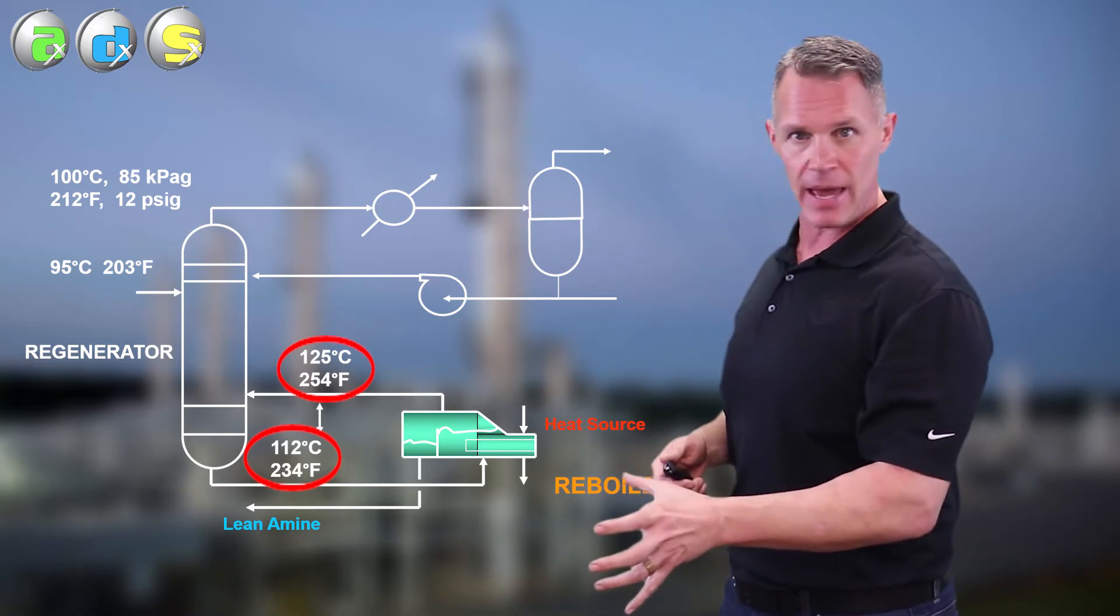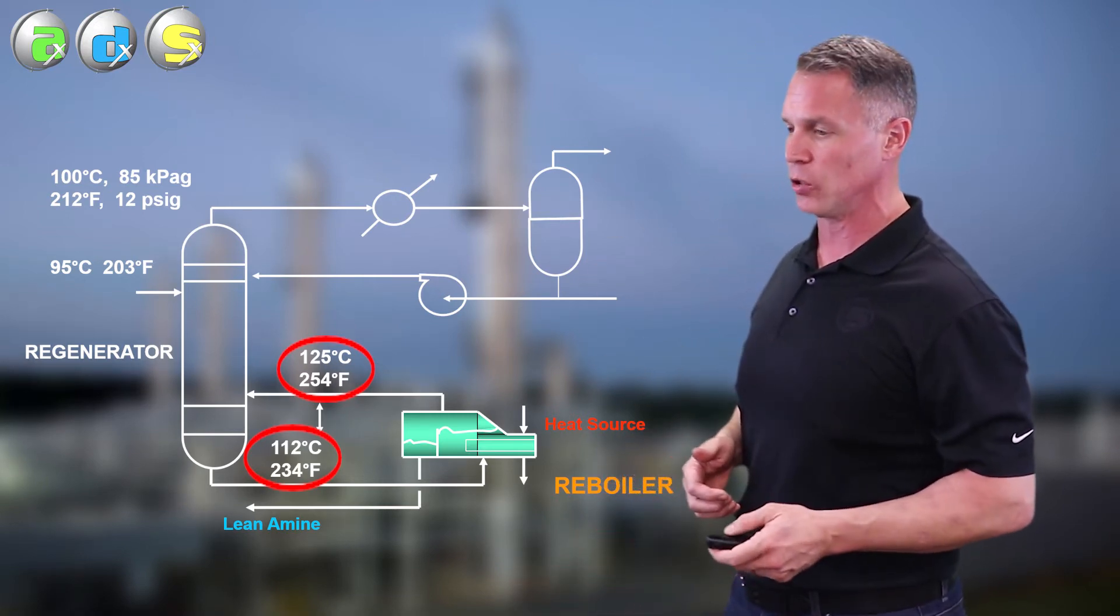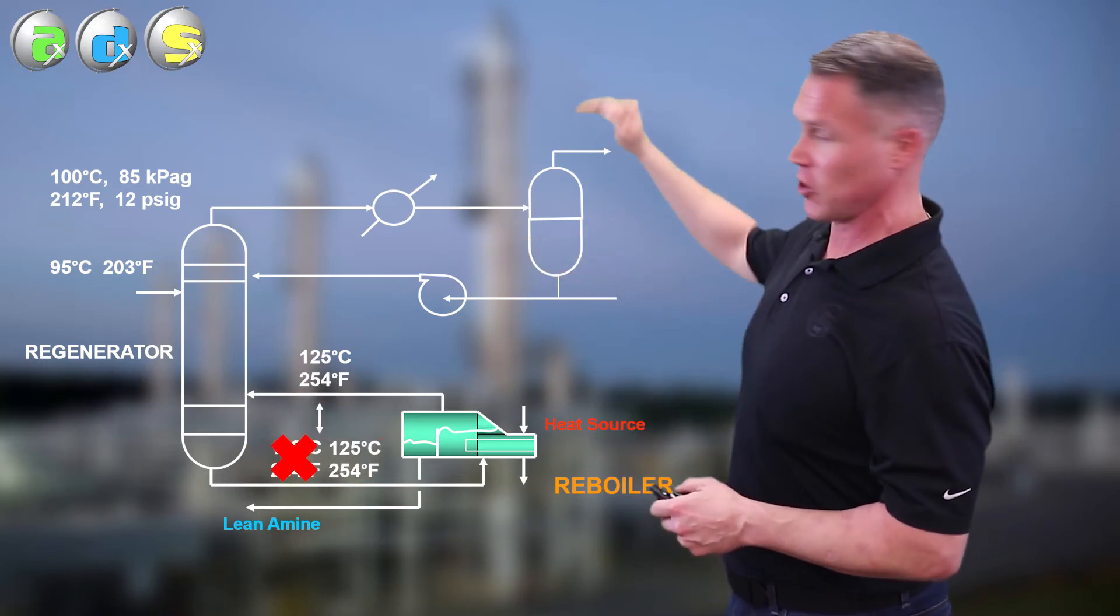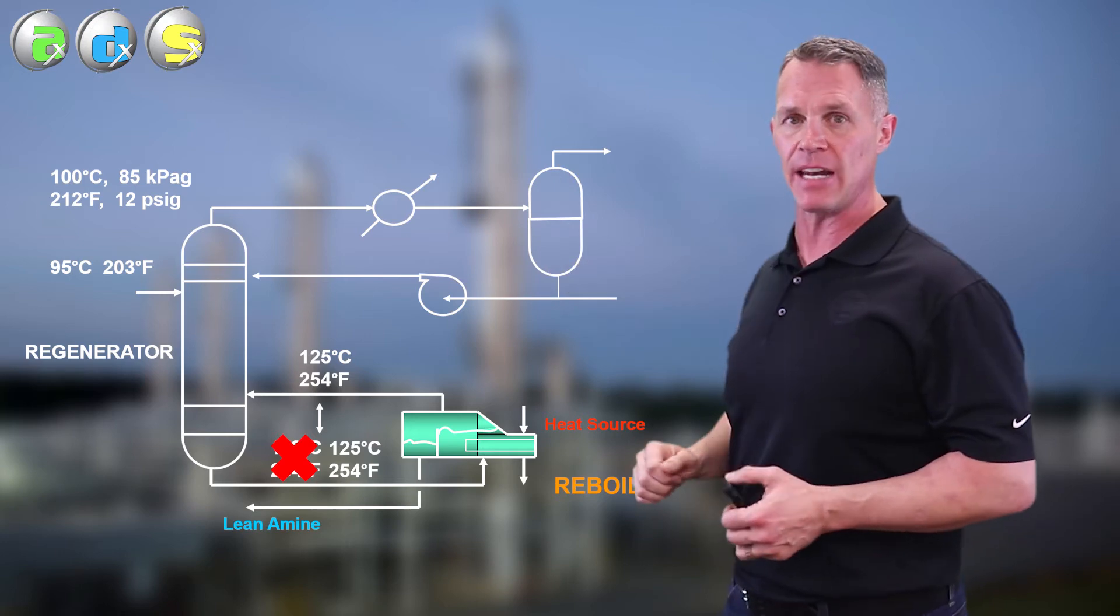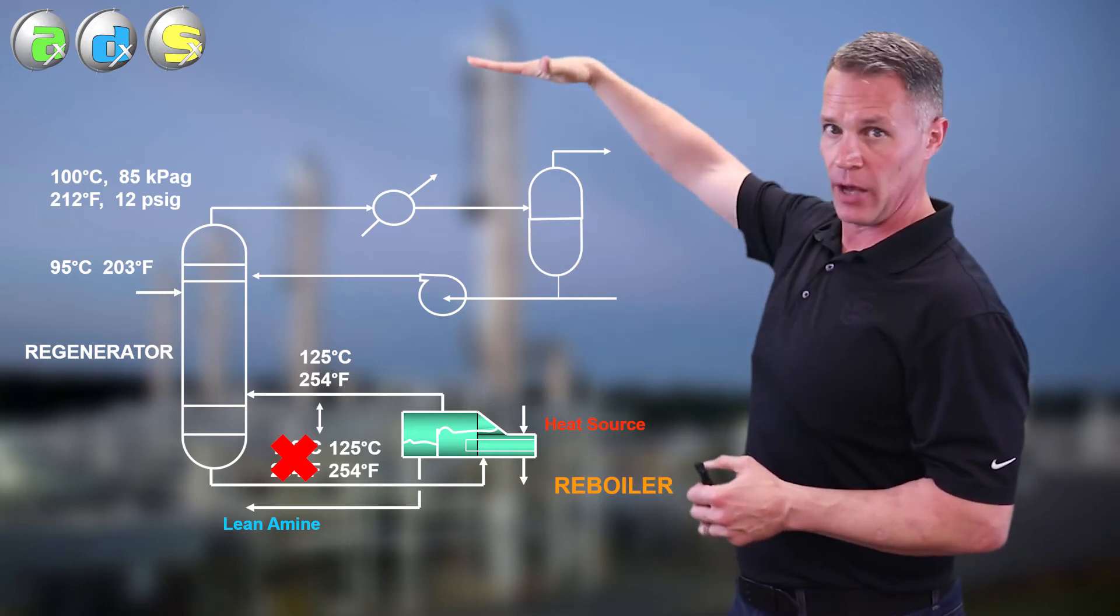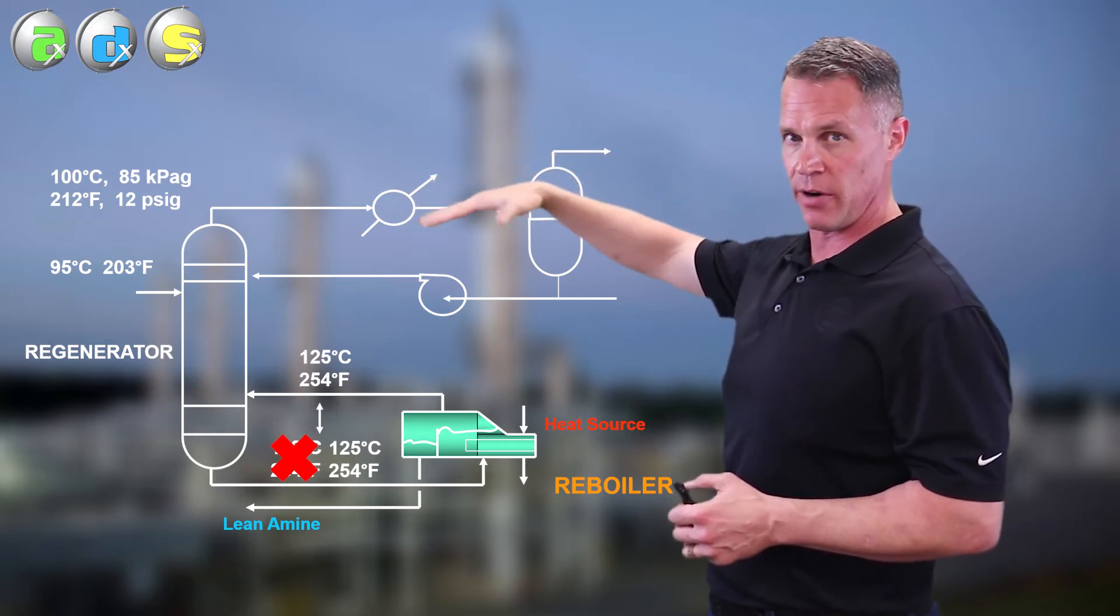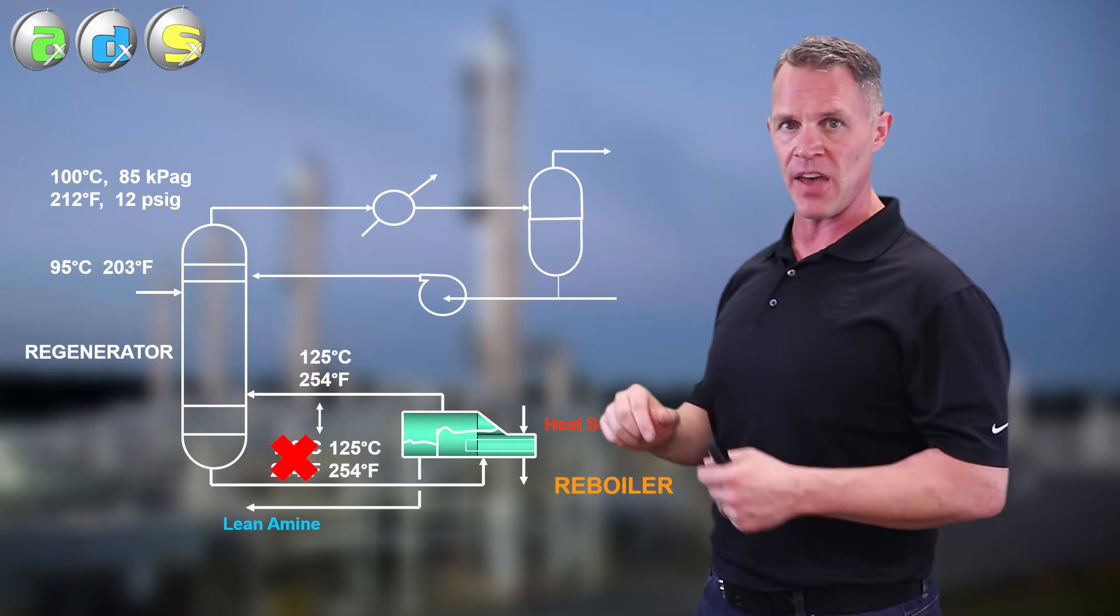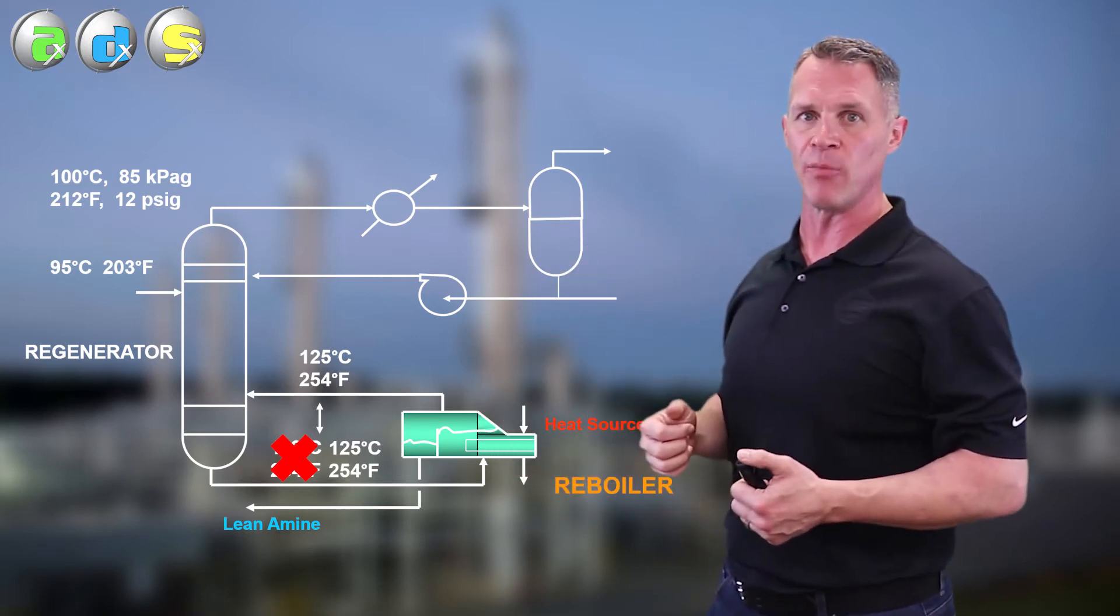In the regenerator, the amine never got heated up the way it was supposed to. So you don't want that. Instead, what you want is this - where the temperatures are about the same in and out of the reboiler. Means the amine, as it flows down those trays or packing of the regenerator, became very, very close to its boiling point. And then we pushed it over the edge in the reboiler itself.